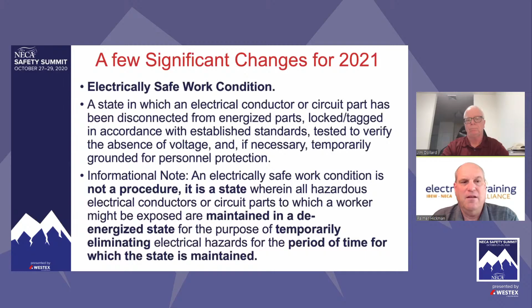But when you get into Article 120, you see it's a lot more than just a definition. Just like with the definition of qualified person, it gives you a high level overview, but until you get into the training that needs to be documented, you don't get the full picture. Article 120 gives you the full picture of the definition of electrically safe work condition, and 110.6 gives you a fuller picture of the training needed to be considered a qualified person. So that's a great informational note clarifying exactly what an electrically safe work condition is.